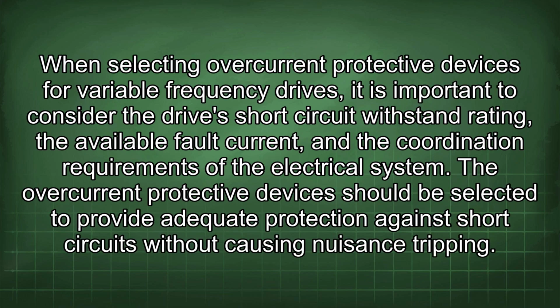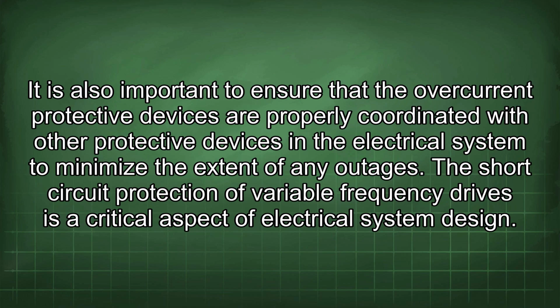When selecting overcurrent protective devices for variable frequency drives, it is important to consider the drive short circuit withstand rating, the available fault current, and the coordination requirements of the electrical system. The overcurrent protective devices should be selected to provide adequate protection against short circuits without causing nuisance tripping. It is also important to ensure that the overcurrent protective devices are properly coordinated with other protective devices in the electrical system to minimize the extent of any outages.